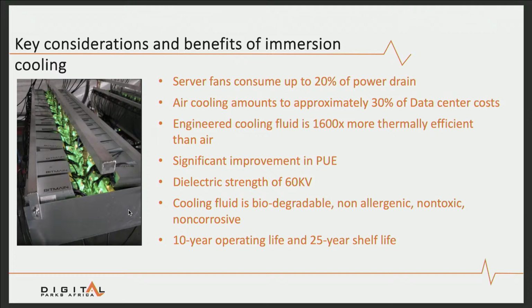They are a little bit more viscous than water, by about 20% more viscosity. Very easy to work with, a very convenient medium. They have about 1,600 times the thermal coefficient of traditional air cooling, so that's really where we get the high density of high performance compute cooling that we can achieve through this technology.